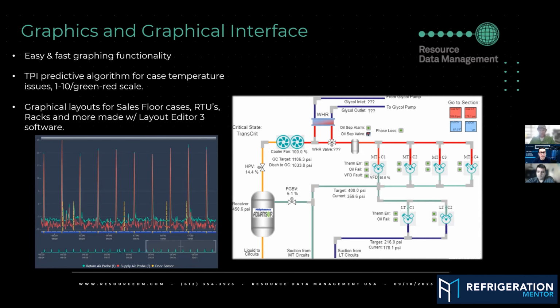Troubleshooting, I think, for technicians, more and more technicians are going to enjoy working on CO2 systems versus HFC systems. And on the CO2 systems, there's a lot of interesting graph data. If you just graph ambient, here it's like 55 degrees right now. On some of these sites, you can see how the flash gas bypass valve modulates down really low because you're not dealing with as much vapor that you have to get rid of in those low ambient conditions. So it's cool to go from a 90-degree day down to a 55-degree day, which happens a lot here in Minnesota. That happens basically every other day.